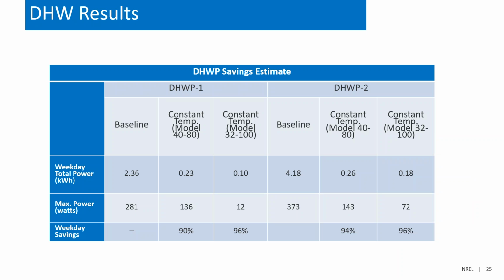So just really quickly on the energy savings. For domestic hot water pump number 1, we saw about 90 to 96% energy savings. Domestic hot water pump number 2 was again 94 to 96% energy savings. And just to reiterate, some of the reasons the savings were so high is because these are the smallest pumps that are manufactured, and they're operating at a very challenging point on that pump curve. So when you can provide a more efficient pump that operates at a better point on the curve, you do get very substantial savings. I would say that this is probably not going to be representative of all domestic hot water recirc systems, but in this case, we did get really good savings on that one.